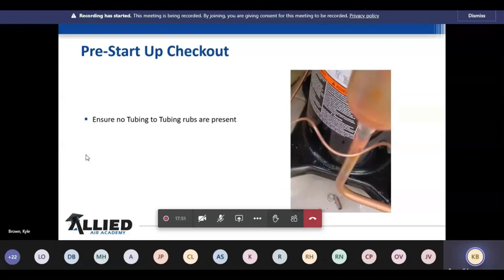Should it be this way from the factory? No. Does it happen? Absolutely. There's not an OEM who's not going to be exposed to this at one point in time or another. But there's a couple things. Number one, I want to make sure everyone inspects the tubing. We have some distributors that take these units and inspect them before they go out to the job site. But if everyone will take a good long look at this picture, they'll see that cap tube, and this is actually a pressure switch tube here, a gauge tube here, laying up against the discharge line right below the muffler. And if you focus on that and you don't see that little piece of copper in the bottom, it'll also make you wonder what happened. Did this unit get reworked?